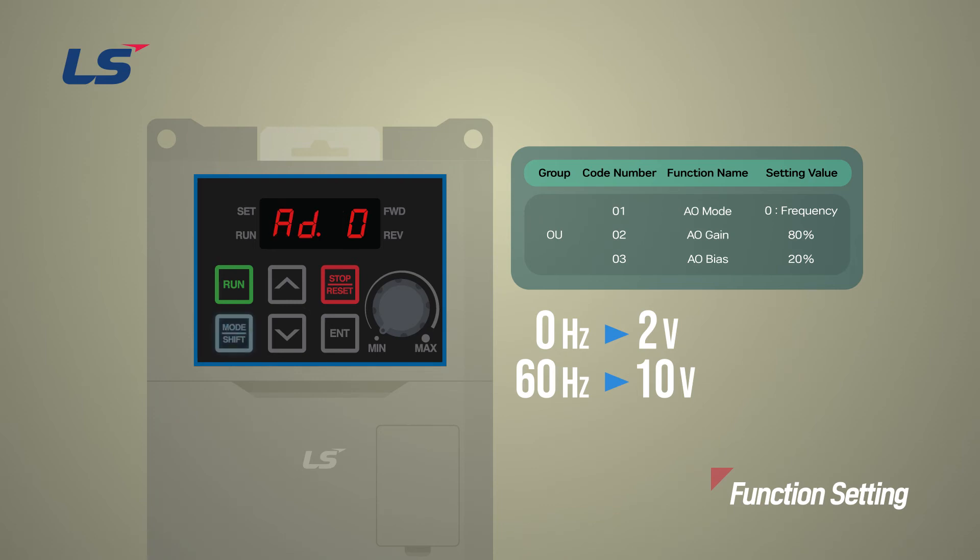First, move to the OU group and set the frequency to zero in AO mode 1. In OU group number 2, AO gain, set the gain for analog output to 80%. And in OU group number 3, AO bias, set the bias value for analog output to 20%.